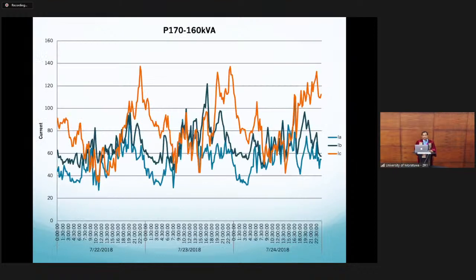Here is the problem. When you take a distribution transformer, it is impossible to balance the three-phase current. A distribution transformer on your roadside has three phases carrying currents, which we termed IA, IB, and IC. In this case IC is pretty high compared to the others, so we can't utilize the transformer fully—one phase gets fully overloaded before the others.